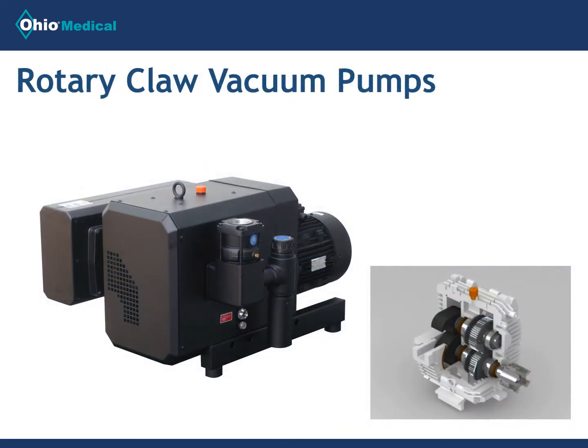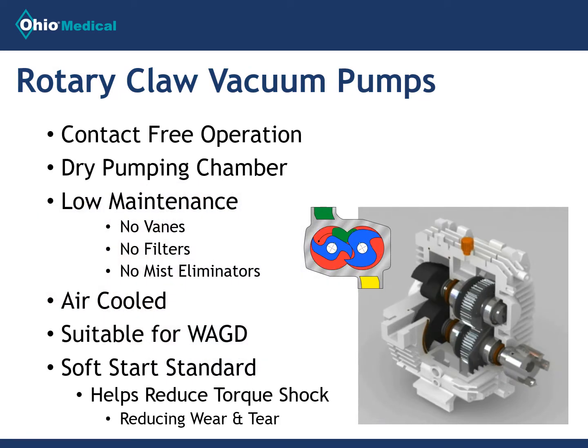One of our most popular styles of vacuum pumps for systems is our oilless rotary claw vacuum pump, ranging in size from 2 to 30 horsepower. The rotary claw vacuum pumps are air-cooled and offer low maintenance with no vanes, filters, or mist eliminators needed. They are suitable for WAGD and feature soft start panels, which lessens wear and tear on the unit.